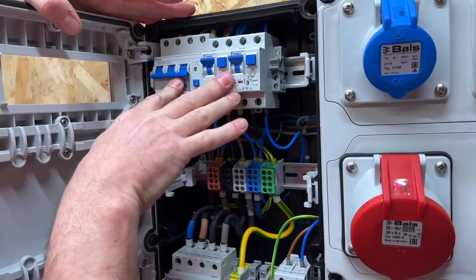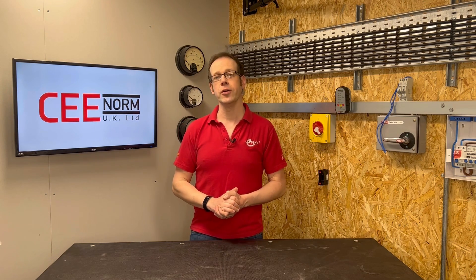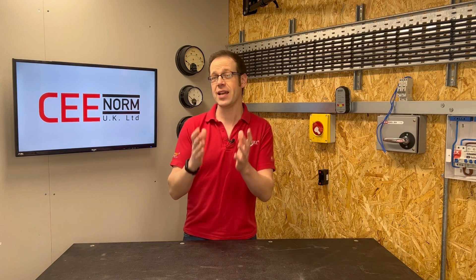There can often be confusion as to whether or not BS7671 actually permits the presence of multiple circuits within a single accessory. This misconception can be understood when looking at division of installation under paragraph 314. Looking at selected points within this paragraph, we can see that installation shall be divided into circuits to avoid danger, facilitate safe inspection, testing and maintenance, and prevent the indirect energising of a circuit intended to be isolated. Upon first review of the wording within this section, it could be assumed that BS7671 seems to suggest separation of all final circuits from one another, which in essence could potentially restrict the wiring of two circuits within a single accessory.